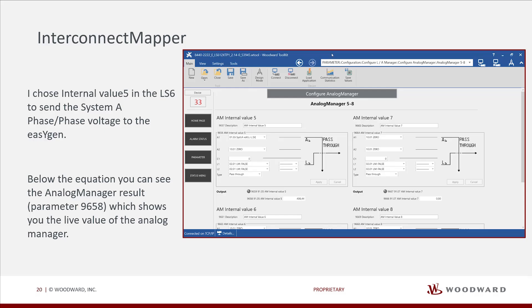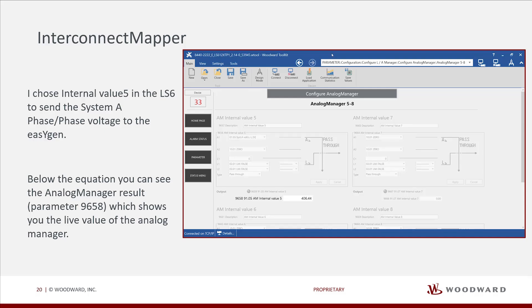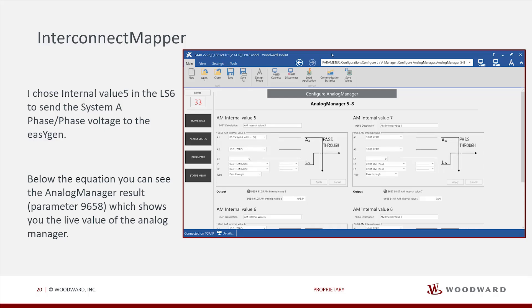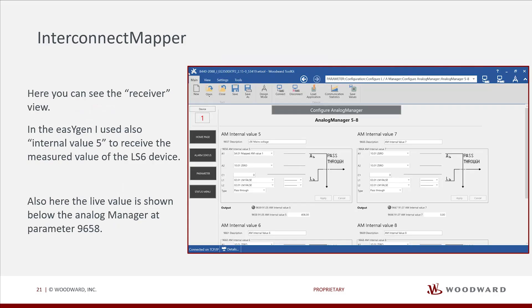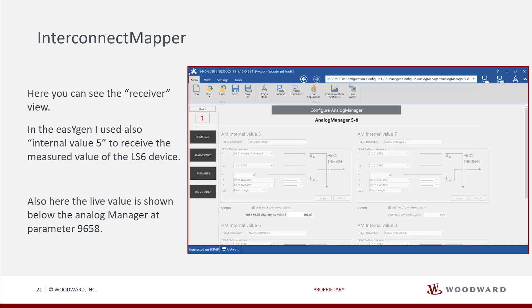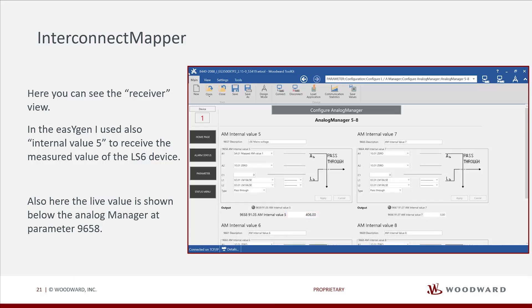Below the equation, you can see the analog manager result parameter 9658, which shows you the live value of the analog manager. Here you can see the receiver view. In the EasyGen, I used also internal value 5 to receive the measured value of the LS6 device. Also here, the live value is shown below the analog manager at parameter 9658.